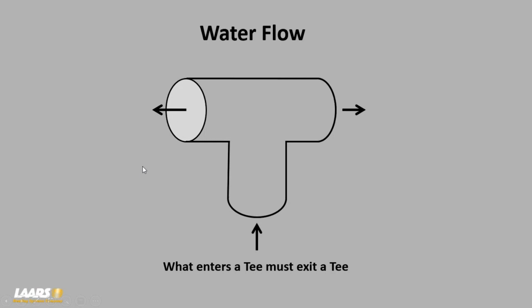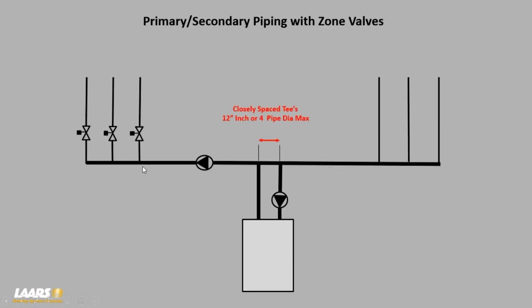So what enters a T, exits a T, if it's sized properly. Those two closely spaced tees should be 12-inch separation or no more than 4 pipe diameter center to center. By doing this, we have no or minimal pressure drop here. Now, I'm also showing a boiler pump.